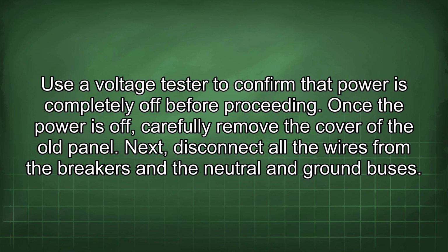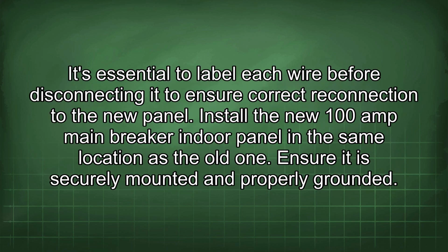Next, disconnect all the wires from the breakers and the neutral and ground buses. It's essential to label each wire before disconnecting it to ensure correct reconnection to the new panel. Install the new 100 amp main breaker indoor panel in the same location as the old one. Ensure it is securely mounted and properly grounded.